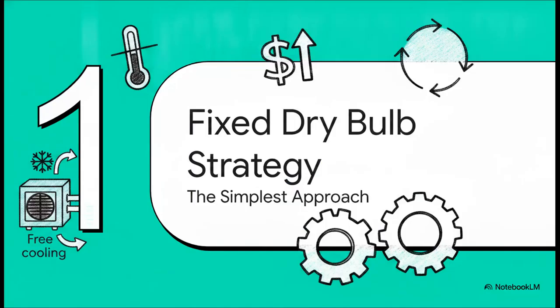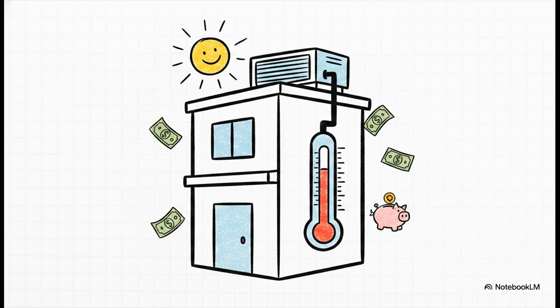Okay, up first is strategy number 1, the fixed dry bulb strategy. This is pretty much the absolute simplest approach out there. The real beauty of this strategy? It's just so incredibly straightforward. It relies on a single basic temperature sensor placed right in the outdoor airstream, and it completely ignores humidity. It acts just like a standard thermometer, taking the sensible air temperature and comparing it to a fixed, predetermined number. And because it's just one basic sensor, it's super cheap to install and requires almost zero ongoing maintenance.